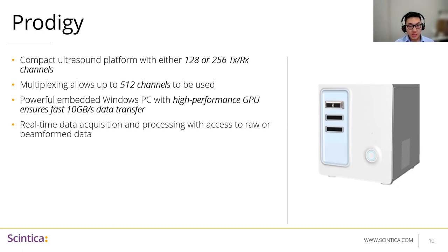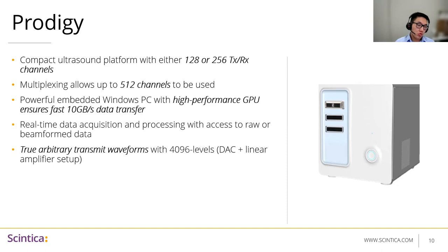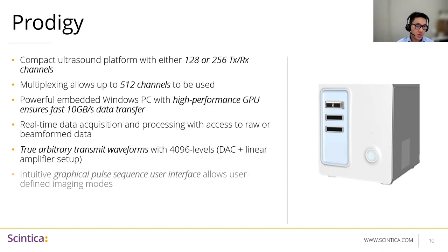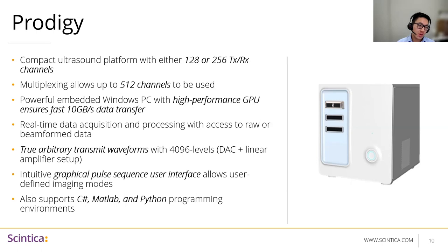There is real-time data acquisition and processing with access to raw or beamformed data. A key feature is the true arbitrary transmit waveform with 4096 levels, made possible by using a DAC with linear amplifier setup rather than just a three-step or five-step system. It also includes an intuitive graphical pulse sequence user interface allowing users to rapidly design and change pulse sequences without needing familiarity with a programming interface. However, the system does support C-Sharp, MATLAB, and Python programming environments to control it and create pulse sequences.